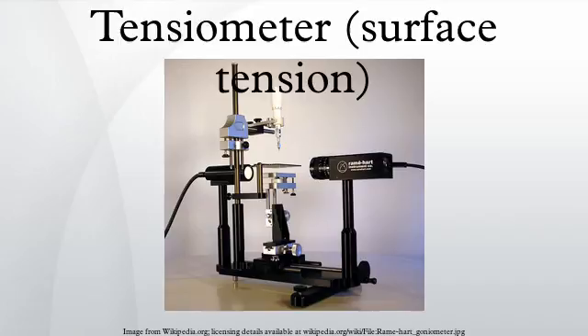Du Noüy ring tensiometer: This type of tensiometer uses a platinum ring which is submerged in a liquid. As the ring is pulled out of the liquid, the force required is precisely measured in order to determine the surface tension of the liquid. This method requires that the platinum ring be nearly perfect. Even a small blemish or scratch can greatly alter the accuracy of the results. A correction for buoyancy must be made. This method is considered less accurate than the plate method but is still widely used for interfacial tension measurement between two liquids.